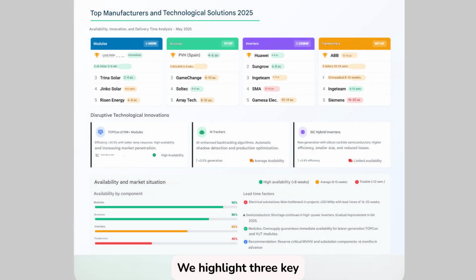We highlight three key advances. TOPCon 670 WP plus modules: efficiency over 24.5%, improved thermal performance, 46% market share by 2025, and high availability. AI-powered trackers: automatic backtracking systems with algorithms that detect shadows and optimize generation. They represent an additional 3.5% in kWh. Hybrid inverters with SiC, silicon carbide: more compact, lower losses, and a 0.8% increase in overall efficiency. Their problem is availability, still limited.